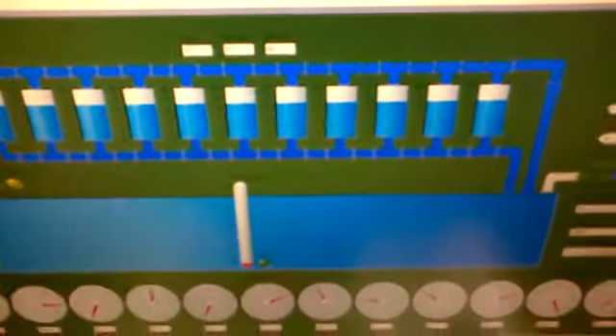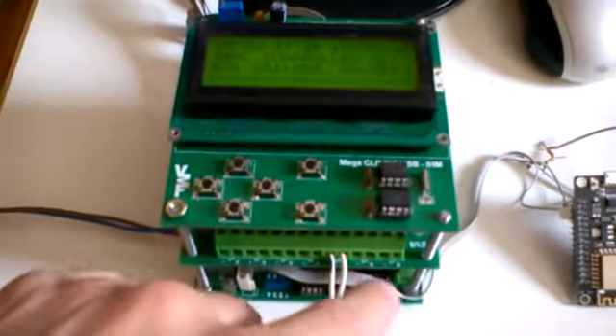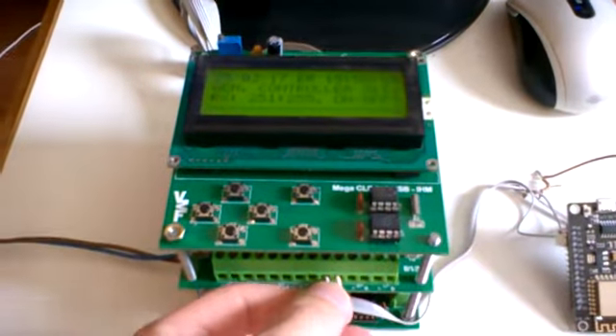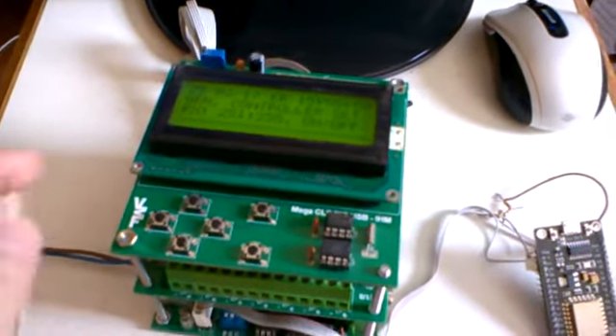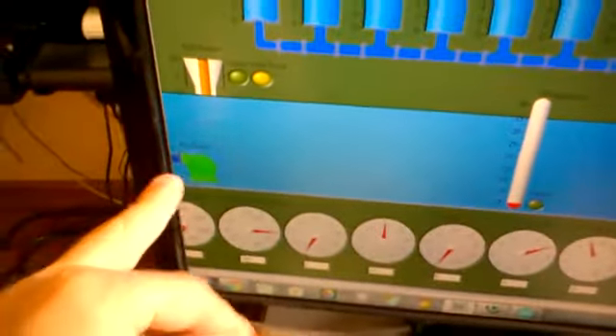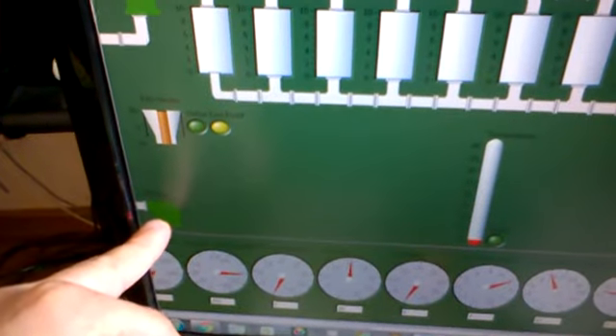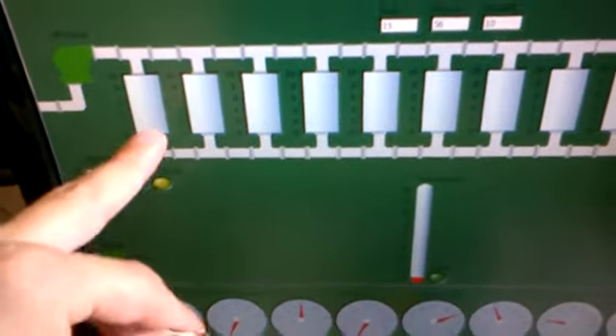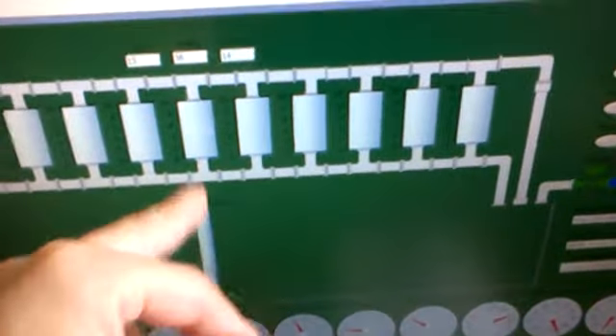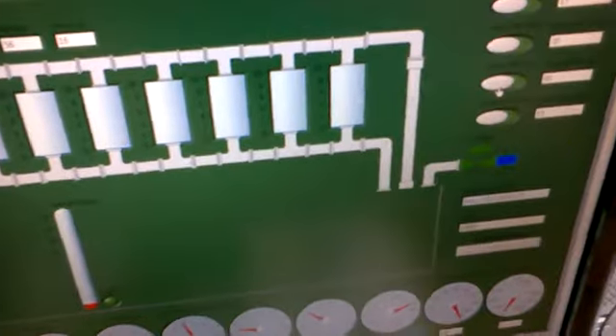Well, so many things to say, but I think I covered most of it. Because I'm using this controller here, my backup controller, I have actually only one input wired and it's the level one. If I unplug that, you can actually hear the relay clicking and it's the relay that's actually in charge of the main pump. So as you guys can see, there's no more flow. This pump is turned off. Everything turns to grey instead of blue.